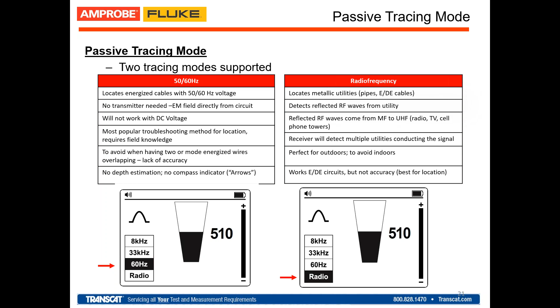Now, if you want more accuracy, or you're in a situation where you're having a lot of noise in radio frequency and you're not having AC power carried by the utility or by the cable, you need to use a transmitter. You need to inject a signal, whether it's an 8 kilohertz signal, 33 kilohertz signal, or 45 kilohertz signal. That's the purpose of the transmitter. What are the three different modes of a transmitter?